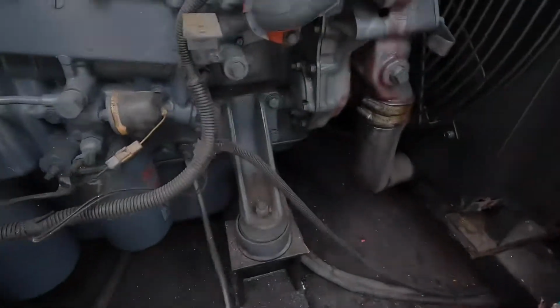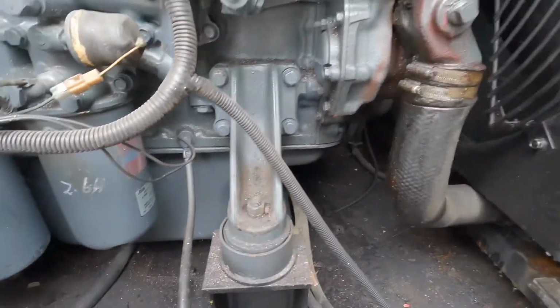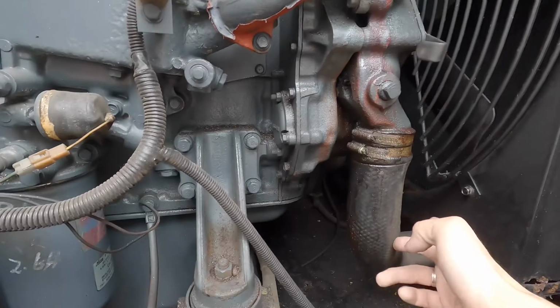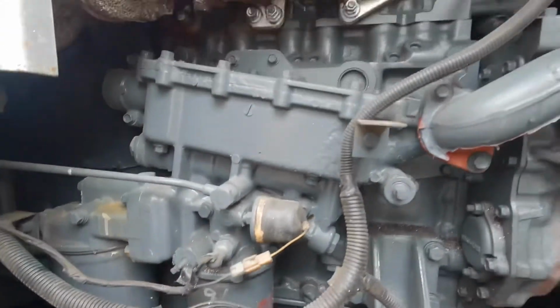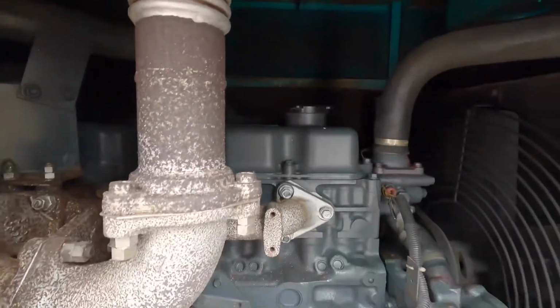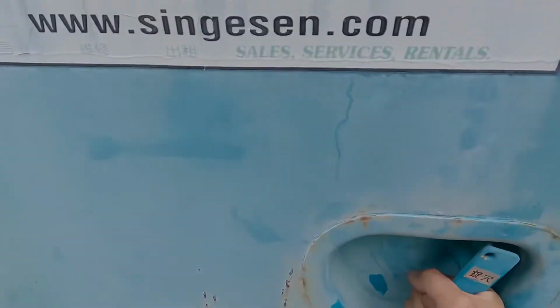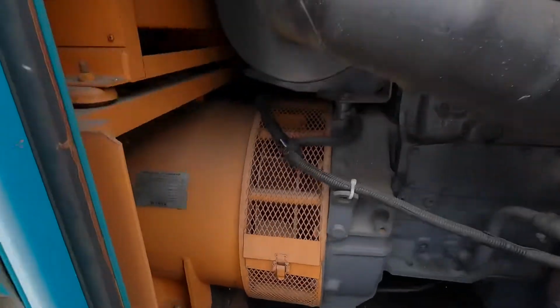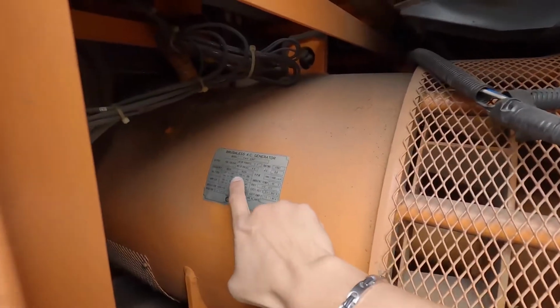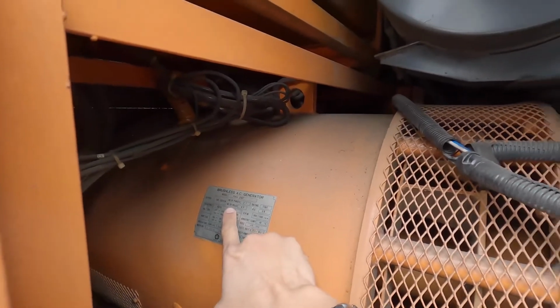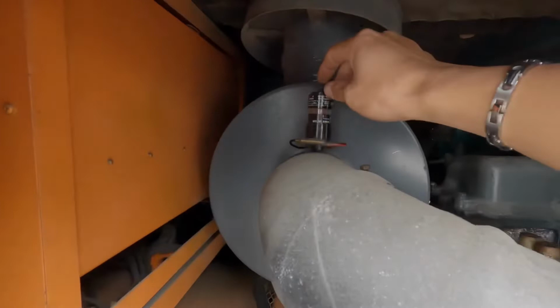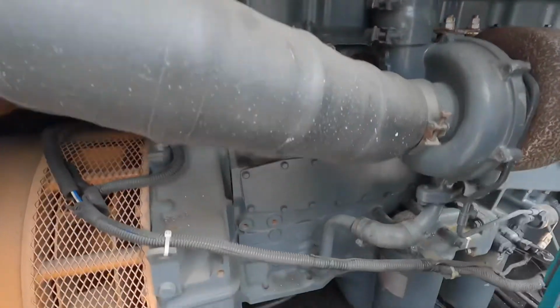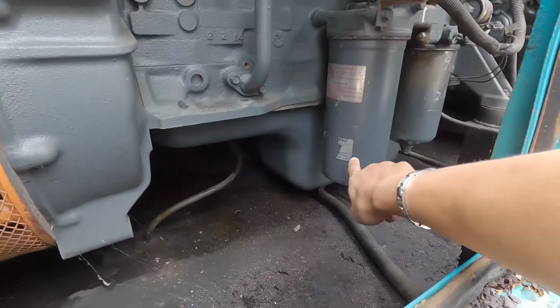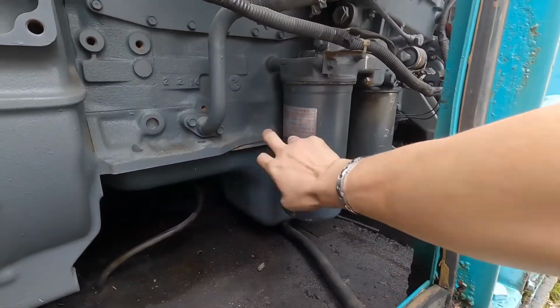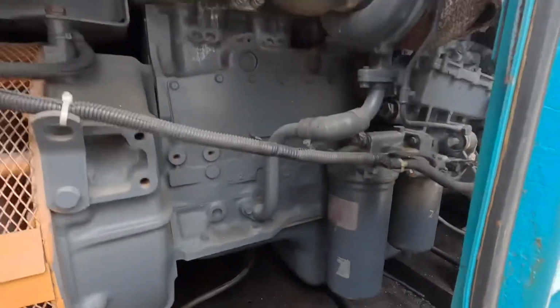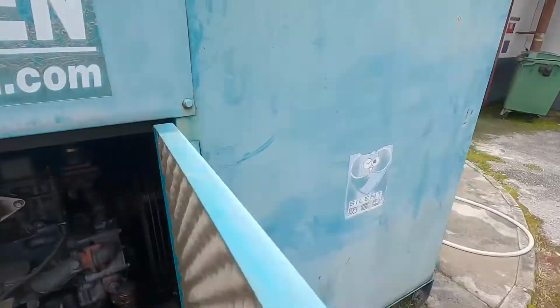Second thing, let's take a look at the genset. Inside here is quite dirty, and there are a lot of signs of radiator water leaking, engine oil leaking, and also fuel leaking. We're going to try to have a test run on it to see whether it can work or not. This is a 125 kVA genset. It's quite cold, the engine. Don't know if it needs warm up or not. There's no date written here, so I don't know when the last servicing date is. Let's take a look at the other side.